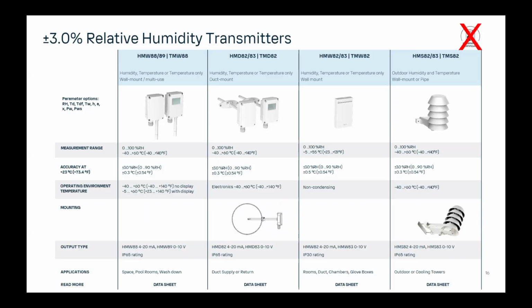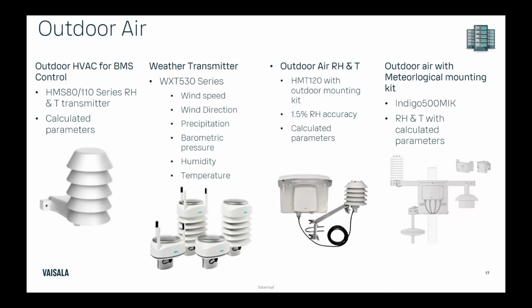So highlighting our outdoor air offering, I'd first like to touch on what it means to be a weather station. So we get a lot of different customers that say, hey, I need a weather station. And my first question is always, okay, what parameters are you looking to measure? And that can mean relative humidity, that can mean temperature, that can mean I want to measure something like the WXT530. The WXT530 is a full weather transmitter. It does wind speed, wind direction, rainfall, snow, barometric pressure, and humidity and temperature. Some people say I need a weather station. They just need the HMS 80 or the HMS 110 series, which is just humidity and temperature, maybe a dew point reading. So weather station is used pretty interchangeably in these industries, but a lot of times they maybe need something more basic or something a little more complex like the WXT530.